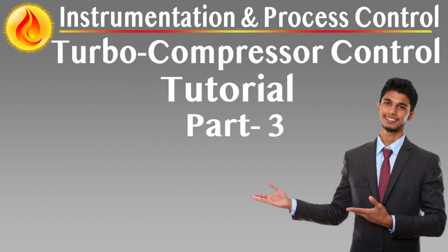Compressor surge prevention and performance management. Dynamic control for surge avoidance, load balancing, and process capacity optimization. Compressor anti-surge control. The Turbo Compressor Control System, TCCS, provides a dedicated anti-surge control strategy for each compressor stage to prevent surge conditions, rapid flow reversals that can damage machinery and disrupt process stability.